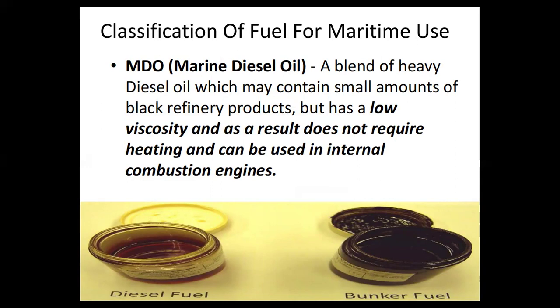This is a blend of heavy diesel oil which may contain small amounts of black refinery products but has a low viscosity and as a result does not require heating and can be used in internal combustion engines. So as compared to your heavy fuel oil, MDO or marine diesel oil has lower viscosity, so it could actually easily flow in our system. Examples of which would be your diesel fuel and at the same time your bunker fuel.